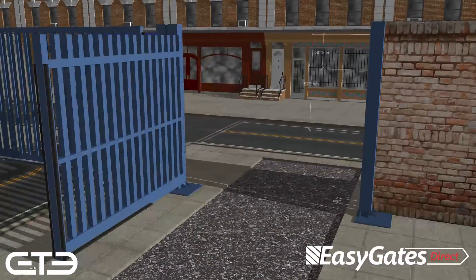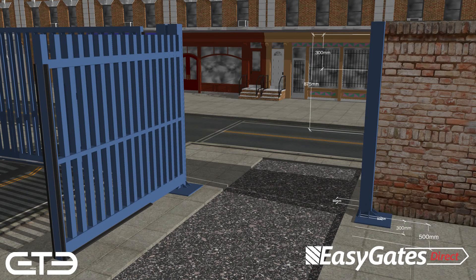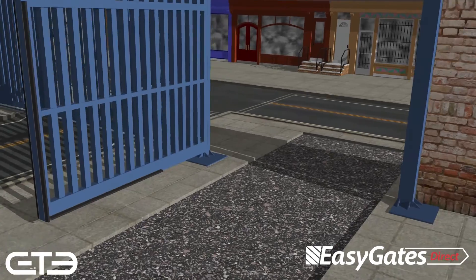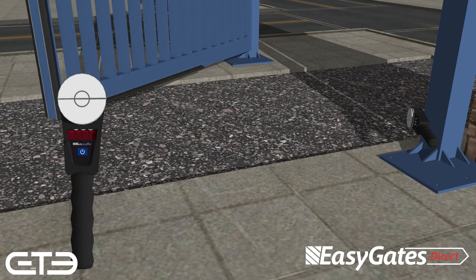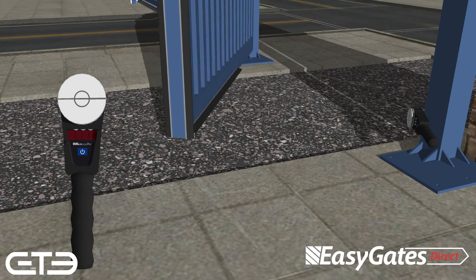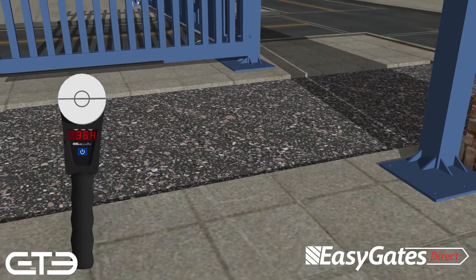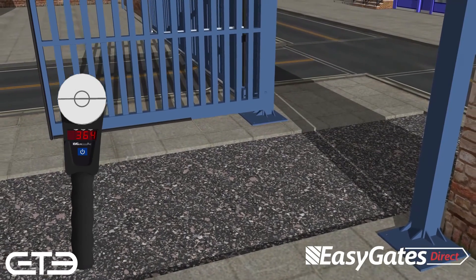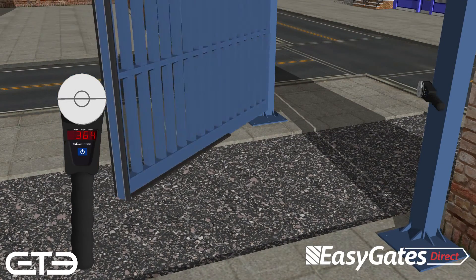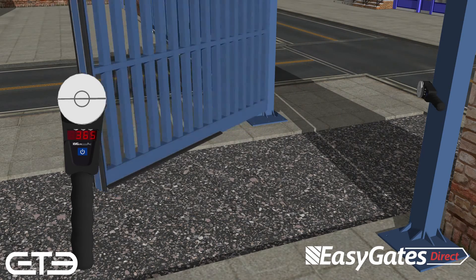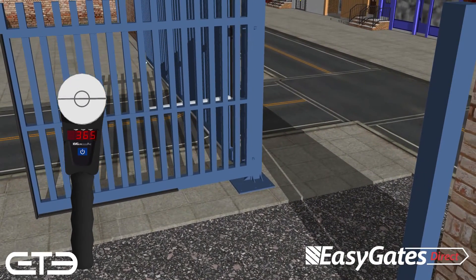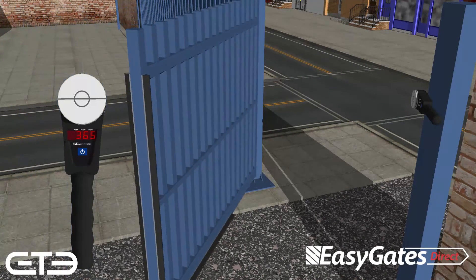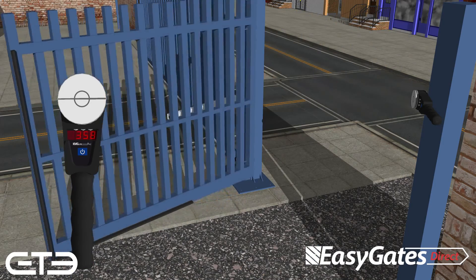Moving on to the swinging gate — these can be a little trickier than the sliding gate, as your measurements must now create an arc following the gate rotation, and the instrument may need to be placed at an angle. To start, place the instrument at 50mm up and 50mm across. Take your readings and record them, then repeat the process two more times. Then again for 300mm down, 50mm across — when all is done you should have nine results and three averages.